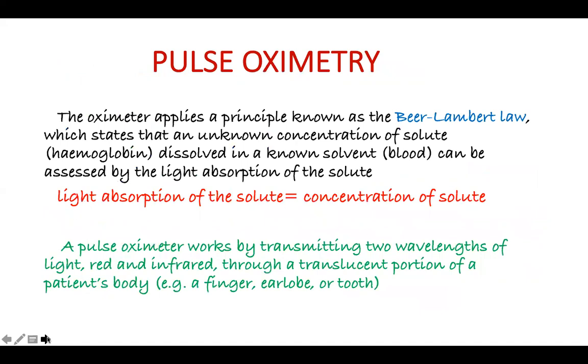The pulse oximeter applies a principle known as the Beer-Lambert law, which states that an unknown concentration of a solute — that is, hemoglobin — dissolved in a non-absorbing solvent can be assessed by the light absorption of the solute. This basically means that light absorption of the solute can be used to assess its concentration. A pulse oximeter works by transmitting two wavelengths of light — red light and infrared light — through a translucent portion of the patient's body, which can be the finger, ear lobe, or the tooth.